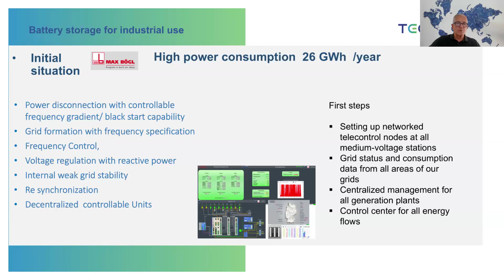You see here they have a huge network, an integrated internal grid, and they are using different kinds of transformer stations. In this example, they have integrated 10 megawatt wind, 2.5 megawatt PV, and a storage system. They installed another 6 megawatt storage system to hold this internal grid as a separate grid and be independent from the power grid. What is also important for such big industrial companies is cybersecurity, and all these internal grids are split up for cybersecurity.